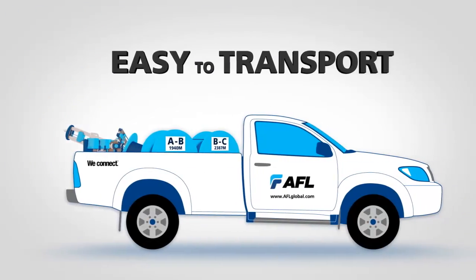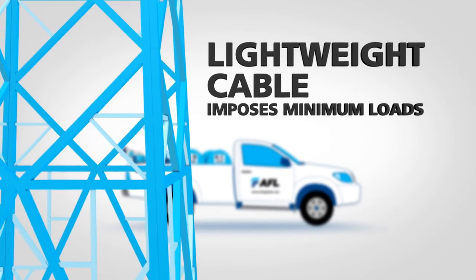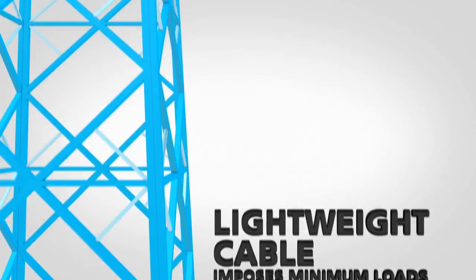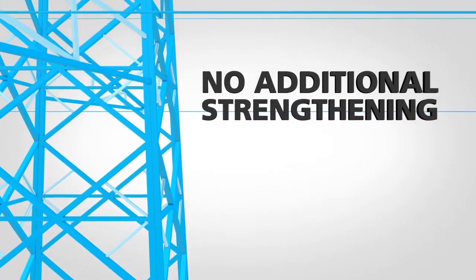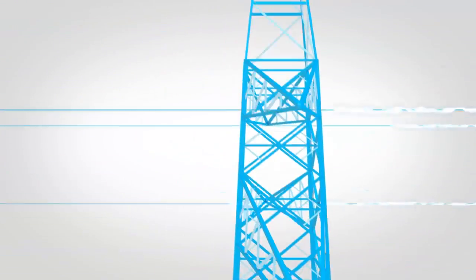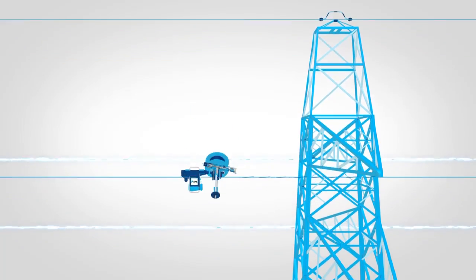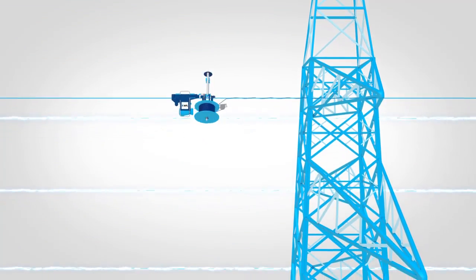Required equipment is basic and easy to transport. The small, lightweight cable imposes minimal loads to existing tower structures, so no additional strengthening is necessary. The cable can be wrapped on the ground wire under live line conditions or phase conductor if there is no ground wire available.